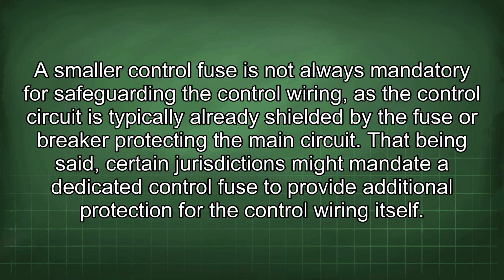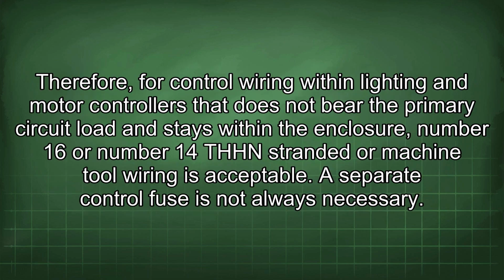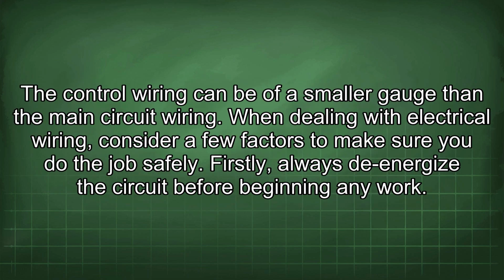A smaller control fuse is not always mandatory for safeguarding the control wiring, as the control circuit is typically already shielded by the fuse or breaker protecting the main circuit. That being said, certain jurisdictions might mandate a dedicated control fuse to provide additional protection for the control wiring itself. Therefore, for control wiring within lighting and motor controllers that does not bear the primary circuit load and stays within the enclosure, number 16 or number 14 THHN stranded or machine tool wiring is acceptable. A separate control fuse is not always necessary. The control wiring can be of a smaller gauge than the main circuit wiring.